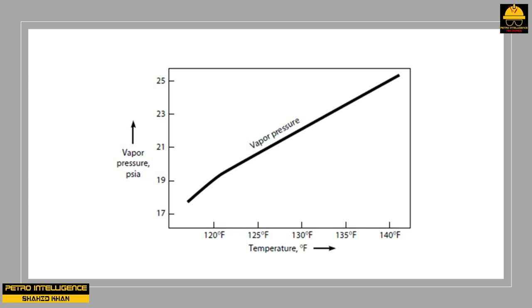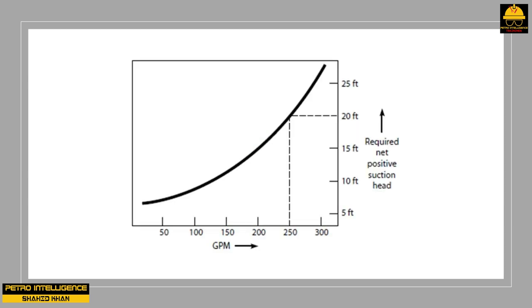Since the specific gravity of the liquid is 0.58, reducing vapor pressure by 2 psi is equivalent to an increase in available NPSH of 8 feet. Our objective is to increase the flow from 250 to 300 GPM; the required NPSH increases from 20 to 26 feet. When we sub-cool the liquid by 5°F, the available NPSH increases from 20 to 28 feet. Since available NPSH now exceeds required NPSH by 2 feet, the flow can be increased without risk of pump cavitation.